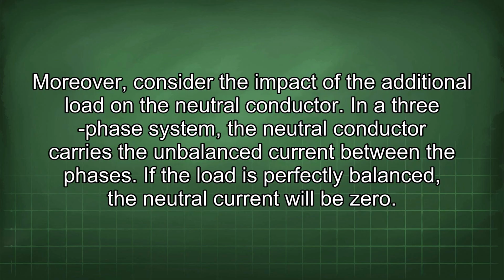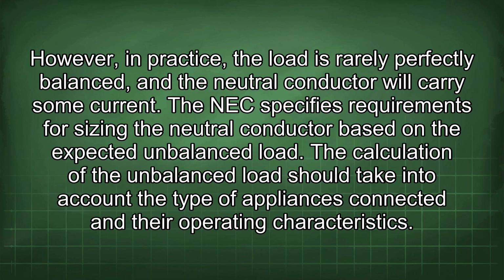Moreover, consider the impact of the additional load on the neutral conductor. In a three-phase system, the neutral conductor carries the unbalanced current between the phases. If the load is perfectly balanced, the neutral current will be zero. However, in practice, the load is rarely perfectly balanced, and the neutral conductor will carry some current. The NEC specifies requirements for sizing the neutral conductor based on the expected unbalanced load. The calculation of the unbalanced load should take into account the type of appliances connected and their operating characteristics.